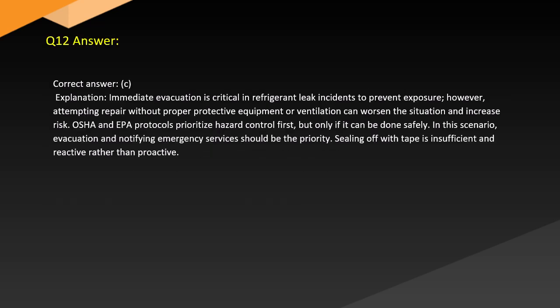Answer. Correct answer: C. Explanation. Immediate evacuation is critical in refrigerant leak incidents to prevent exposure. However, attempting repair without proper protective equipment or ventilation can worsen the situation and increase risk. OSHA and EPA protocols prioritize hazard control first, but only if it can be done safely. In this scenario, evacuation and notifying emergency services should be the priority. Sealing off with tape is insufficient and reactive, rather than proactive.